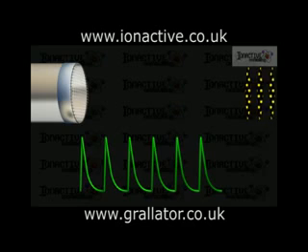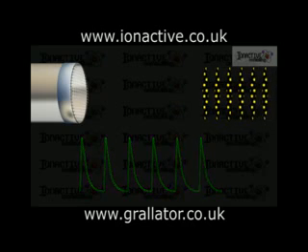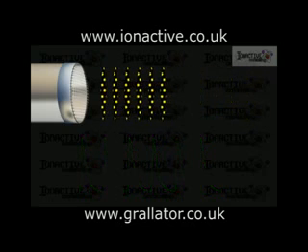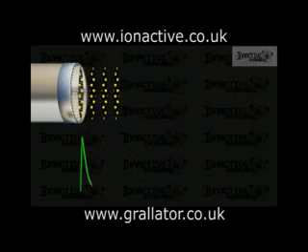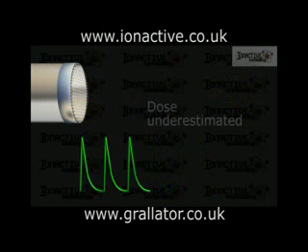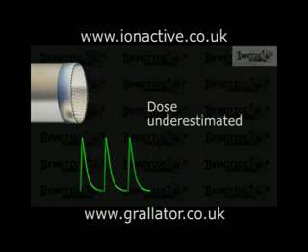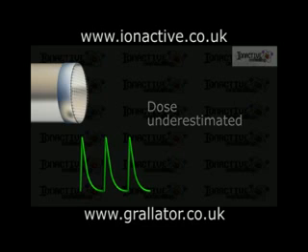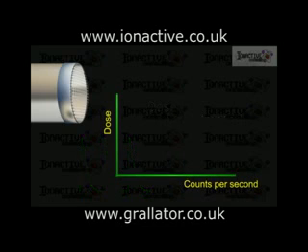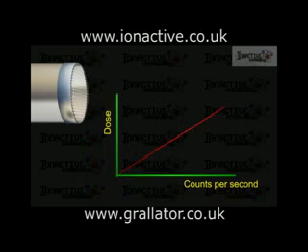If the dead time is significantly longer than the bunch frequency, the detector will count only a fraction of the bunches, leading to a further under-reading. If the operating characteristics of the GM tube and the LINAC are known, these effects may be compensated for so that a GM tube could be used. This will mean, however, that a different detection method has been used to initially calibrate the data.